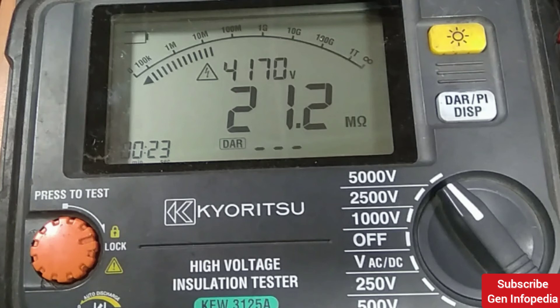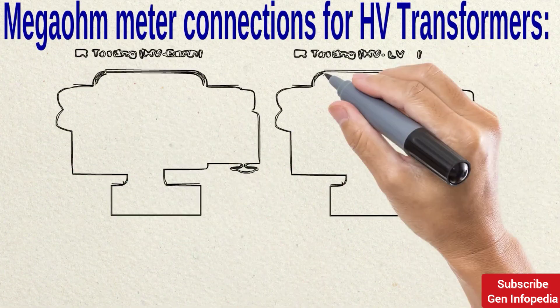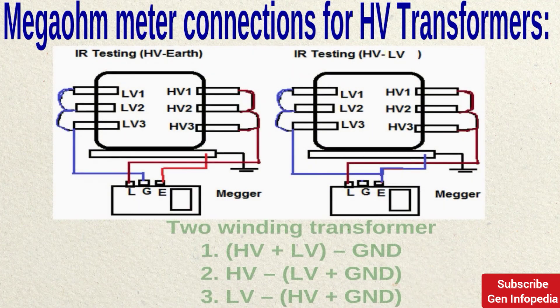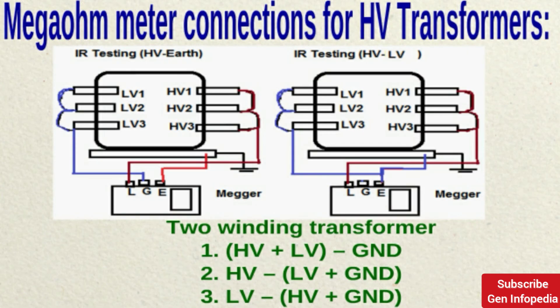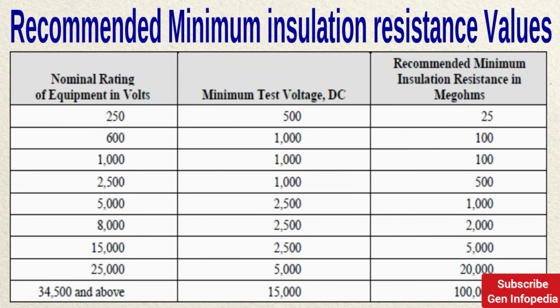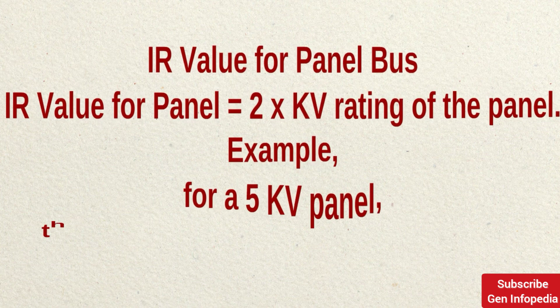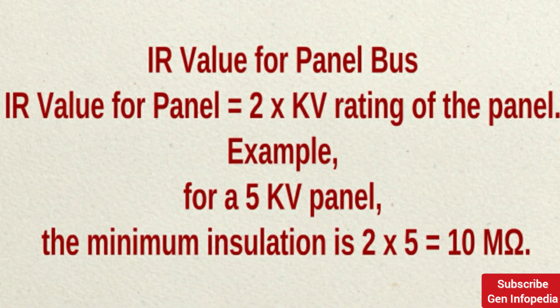You will see readings showing the insulation resistance value. These connections also apply when measuring insulation resistance for high voltage transformers — the first picture shows connections for HV to earth, and the second shows HV to LV. There are recommended minimum insulation resistance values based on equipment voltage ratings. For example, for 250 V equipment, the minimum test voltage is 500 V DC and the recommended minimum IR value is 25 MΩ. For panel busbars, the formula is: minimum IR (MΩ) = 2 × kV rating of the panel. For a 5 kV panel, that is 2 × 5 = 10 MΩ minimum.